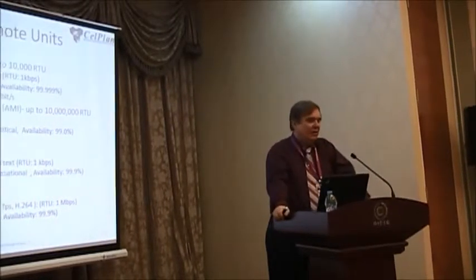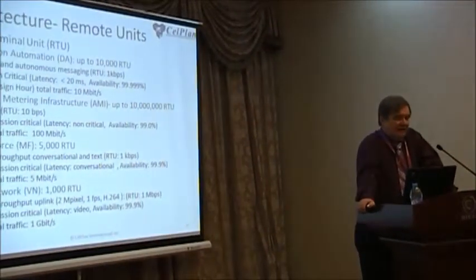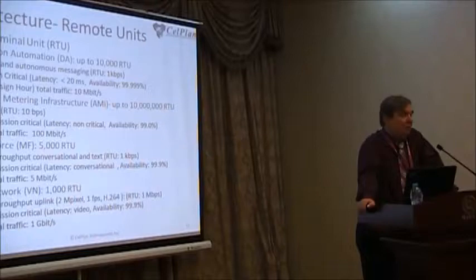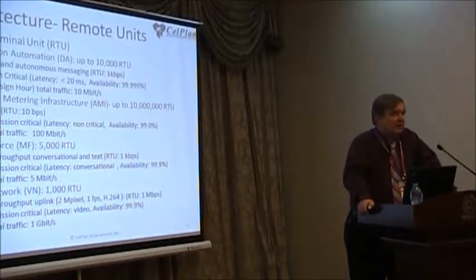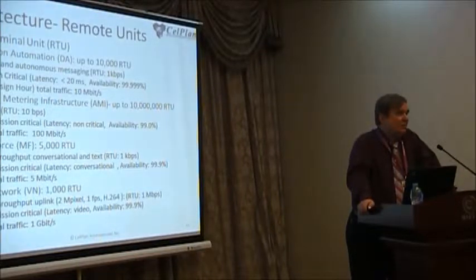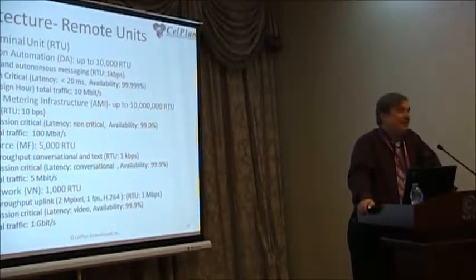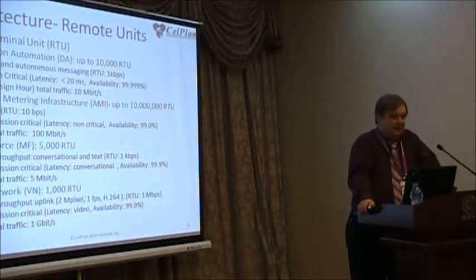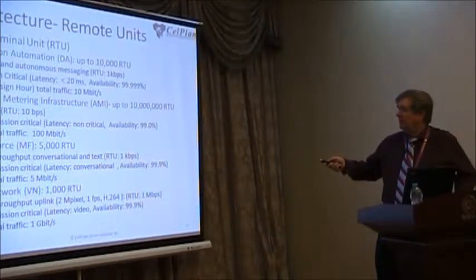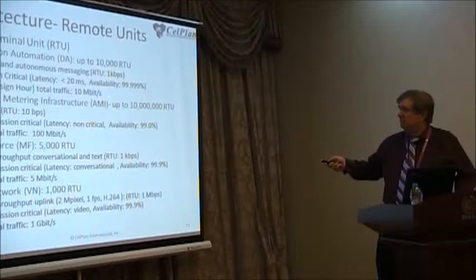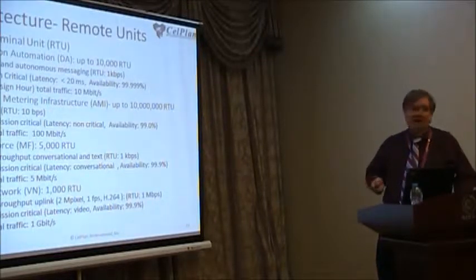This is the network that you have to control for automation of the network, so this is very critical - mission critical. It's low data rate, and the advantage of being low data rate is that you can use a very robust protocol, repeating information several times. That's what allows you to provide the availability required, because wireless by itself is intrinsically unavailable - it has fadings and things like this that you have to design for. So: 10,000 points, 20 milliseconds, design hour, busy hour, 10 megabits per second.